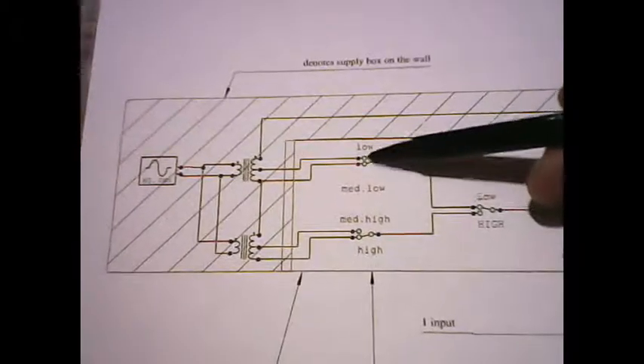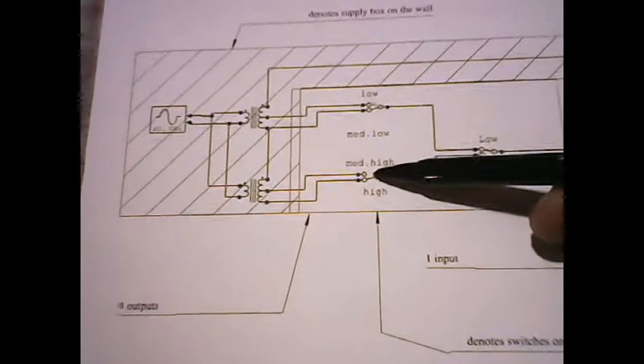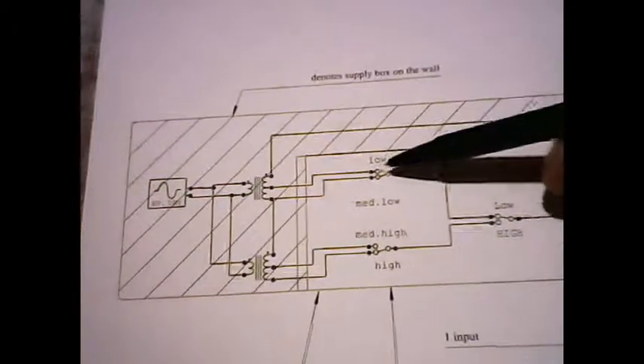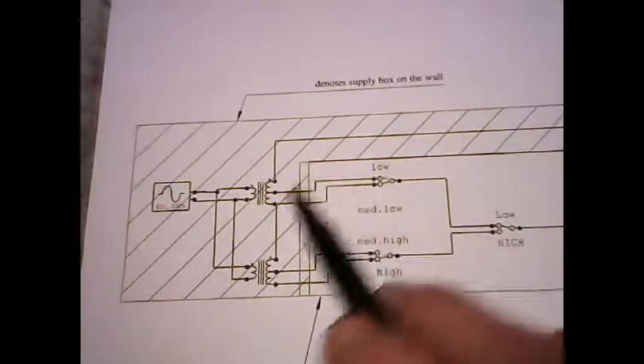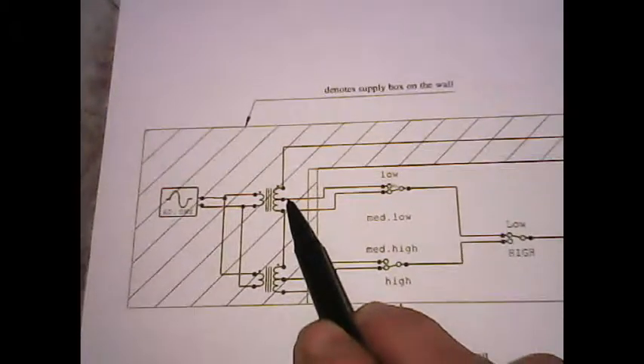This selector switch here is for low and medium-low. This selector switch here is for medium-high and high. The reason is because when this is in the up position, only half of the first transformer comes on.